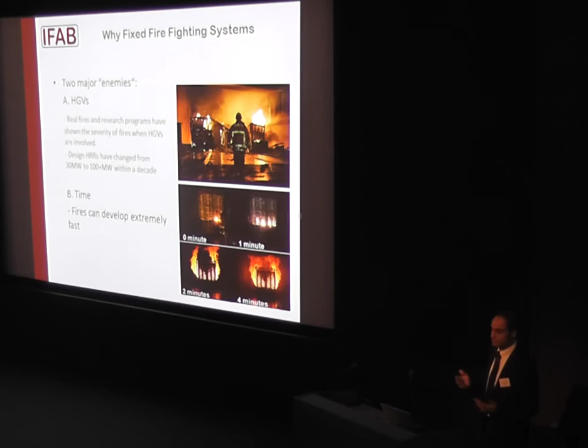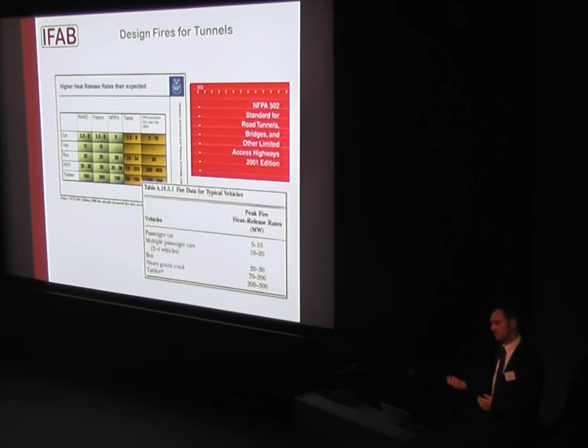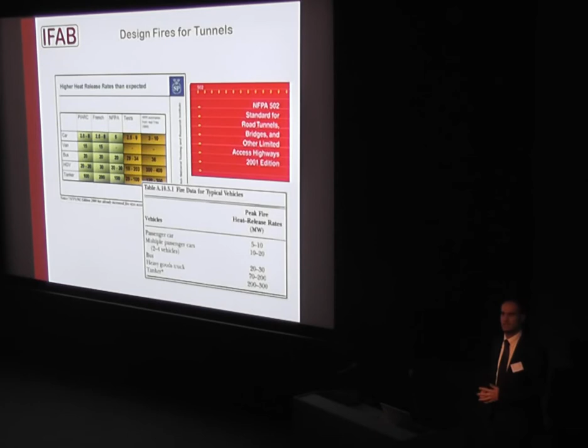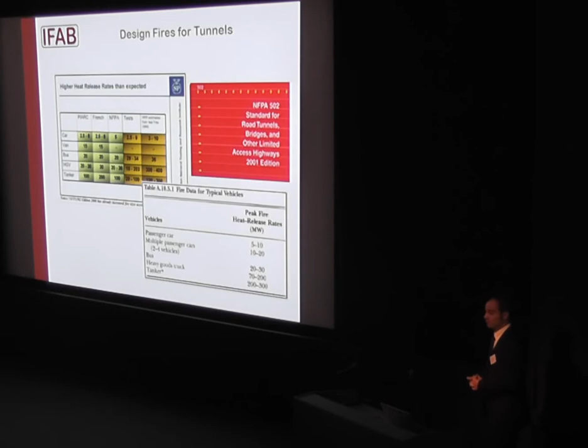You arrive 6-8 minutes on the highway with, let's say, a bus or a truck, and the truck is on full fire. And of course, this can also happen inside tunnels. That's why in the past, or at least it's now starting to be introduced into guidelines like NFPA, and the Europeans are slow but intending to change that too, the design fire rates or heat release rates in the guidelines are changing. In the past it was strictly 30 megawatts, and now we are going up to 100, even 200 megawatts in some special cases. But that's the real life, and that's the truth.